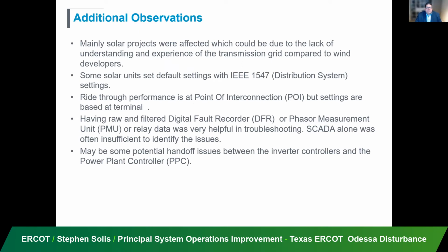Some additional observations, just to highlight, we've talked through most of these things, but solar seems to be learning while wind has been already on the system for a few years, and we've worked out some of those issues. But the solar resources are coming, and they're coming fast, and they're experiencing more issues right now like this. These are more major events. We're seeing regular disturbances, maybe 2 to 3 times a month, smaller losses of about 100 megawatts that are occurring on the system. So this is quite frequent that we're seeing unexpected reductions in megawatts due to faults on the system.